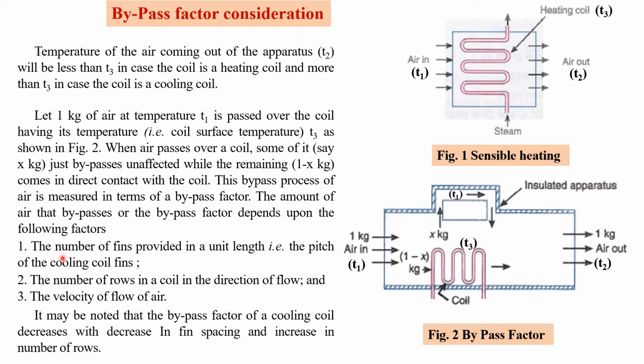So here we have three vital parameters which affect the amount of bypass: the number of fins provided in a unit length, that is the pitch of the cooling coil fins, the number of rows in a coil in the direction of flow, and the velocity of flow of air. It may be noted that the bypass factor of a cooling coil decreases with decrease in fin spacing and increase in the number of rows.